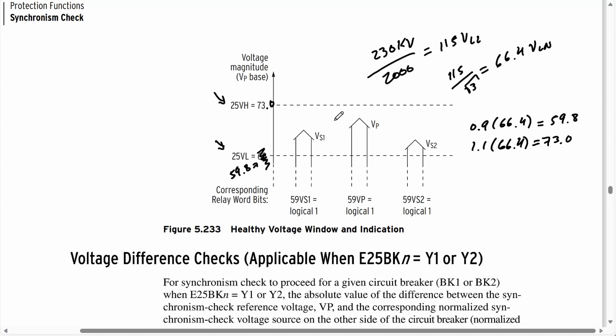And then the relay takes measurements of the frequencies as well, and we're allowing a close if that difference is not greater than 0.05 hertz. And we're also saying that the angle difference at the moment the breaker closes cannot be greater than 20 degrees when we're doing an auto reclose, or 30 degrees when we're doing a manual close. Now the output of the sync check logic is relay word bit 25A1BK1, and this is of course for breaker number 1, and this takes into account the time it takes for the breaker to close if the frequencies are slipping, so that we look at the angle difference at the moment the breaker closes, not at the moment when the close signal is issued. And again, the relay knows that because it knows what the maximum slip frequency is, and it knows what the closing time of the breaker is.